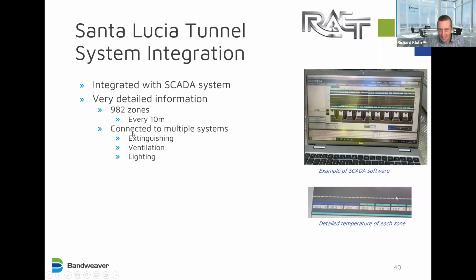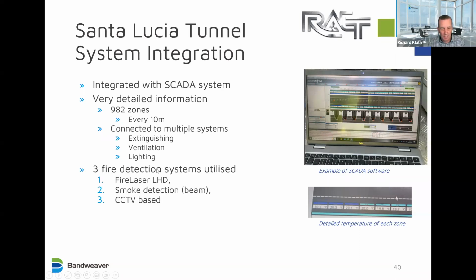So it's connected to multiple systems, the extinguishing, ventilation and lighting, but the extinguishing required every 10 meters. And the fire detection systems are also linked to the smoke detection and CCTV, but only the fire laser was used for alarming because it could divide the tunnel into 10 meters and then link back to the extinguisher. So it really is an absolutely critical system for Autostrade in this tunnel.